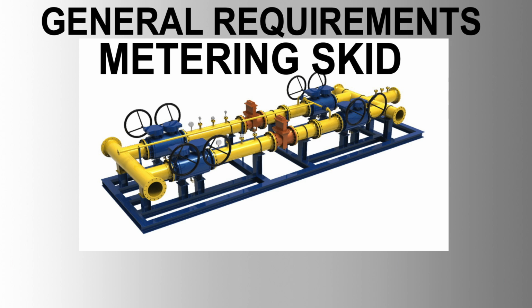4. Calculations and additional specifications. Metering calculations. Meters must conform to relevant calculations for accuracy and stability, complying with API Manual of Petroleum Measurement Standards. Pulse fidelity should be maintained, with dual transmission verification to ensure continuous accuracy. Pressure drop across the metering system should be minimized, not exceeding 1 bar without control valves and 2 bars with control valves.